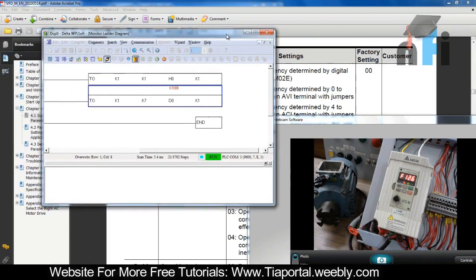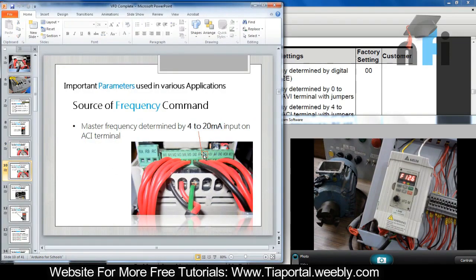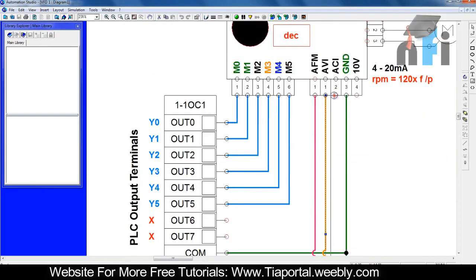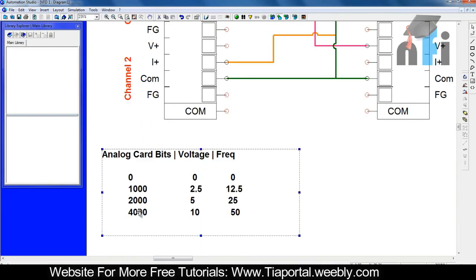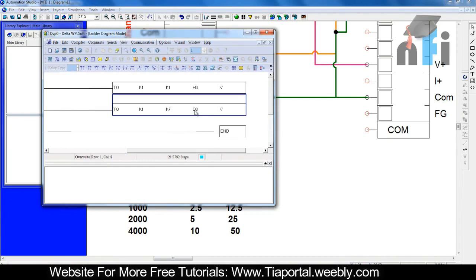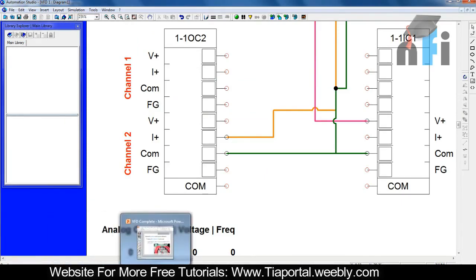That was about changing frequency by AVI terminal using 0 to 10 volts. The next option is master frequency determined by 4 to 20 mA on ACI terminal. For ACI, we connect AVI to ACI and switch the terminal from V+ to I+ terminal, because I+ gives 4 to 20 mA. The same bit range of 0 to 4000 applies - in the same range you get 0 to 10 volts from AVI or 4 to 20 mA from ACI. You just change the wire and switch the mode to current input; the same bit values of 0 to 4000 control the frequency.